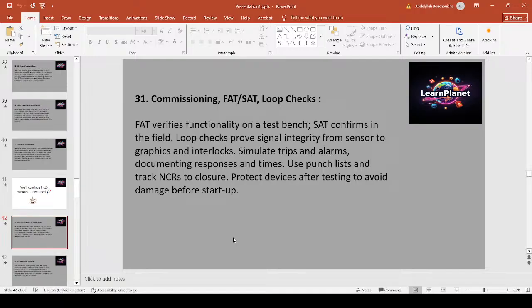Commissioning, FAT, SAT, loop checks. FAT verifies functionality on the test bench. SAT confirms in the field. Loop checks prove signal integrity from sensor to graphics and interlocks. Simulate trips and alarms, documenting responses and times. Use punch lists and track NCRs to closure. Protect devices after testing to avoid damage before startup.